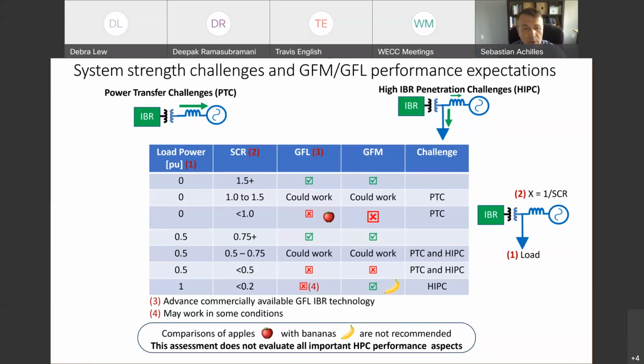With that, let's get to the last one, where we assume that the load is 1 per unit. So the load is consuming all the power injected by the inverter-based resource, and the short circuit ratio, let's say, is below 0.2. In that case, it's quite likely that the grid following will not work, and it's typically an expectation that the grid forming will work. So this is kind of the differentiation. The short circuit ratio is very low. There is no power transfer challenge. And here the grid forming is expected to do better.